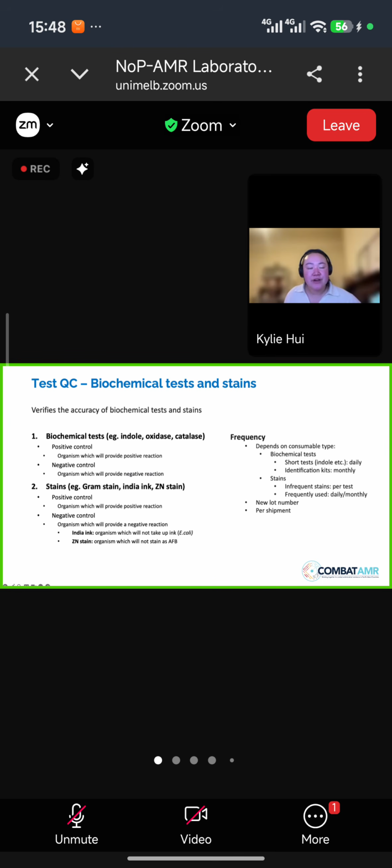Yeah, so if they don't have an expiry date, it's really important to run the QC in parallel to your test. It depends on the frequency of when you're getting these requests. I know for my lab, it's quite rare sometimes, and having that Cryptococcus handy in the incubator means you can just take it out and run the QC as you're doing a patient sample. That should be enough to give you confidence that it's working. It is tricky when they don't give you an expiry, but doing that daily QC will give you confidence that it's still working as it should.